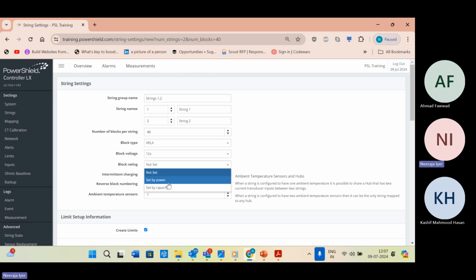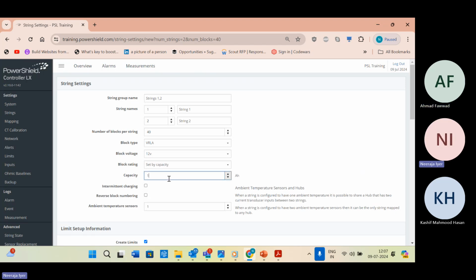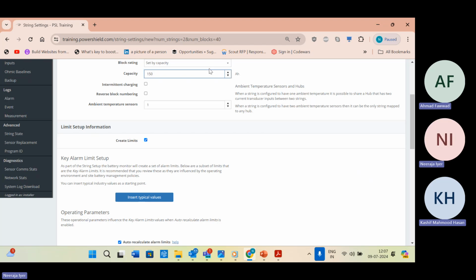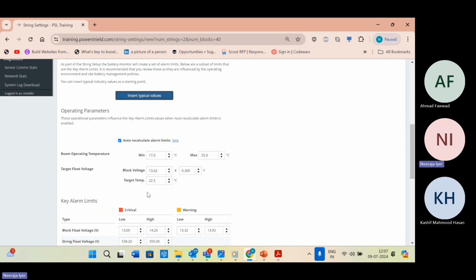You can set the capacity of the battery, and it is 150 Ah. I'm just giving you an example, it could be 200 also. Ambient temperature is 1. There is no intermittent charging or reverse block numbering because you are connecting the blocks in series anyway. And then these are the alarm limits. Insert typical alarm limits if you use them. We have our own calculated alarm limits.